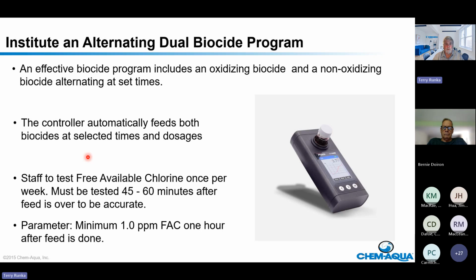Now, the nice part is your controllers are set up to feed however we've decided to feed your biocides, for how long we feed them, based on how much water there is, the type of water, what we're looking at. What we've asked the staff to do is once a week minimum, test your free available chlorine levels in the cooling towers. Now, the trick is, because we're feeding it on a slug feed, which is the most effective, and 95, 98% of places feed that way, you have to measure it 1 hour after the chlorine feed is done. So you have to know when the chlorine feed is.